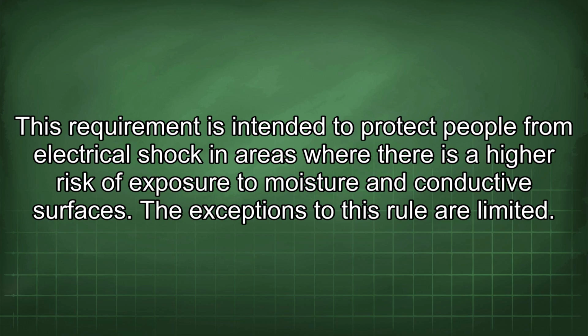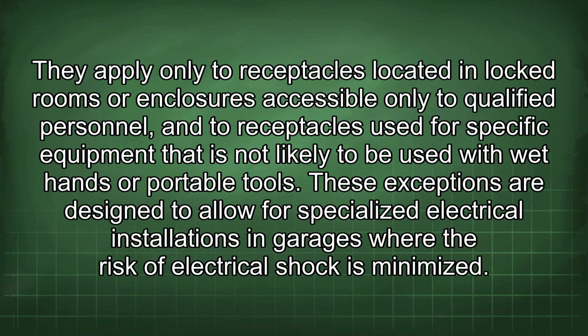The exceptions to this rule are limited. They apply only to receptacles located in locked rooms or enclosures accessible only to qualified personnel, and to receptacles used for specific equipment that is not likely to be used with wet hands or portable tools. These exceptions are designed to allow for specialized electrical installations in garages where the risk of electrical shock is minimized.